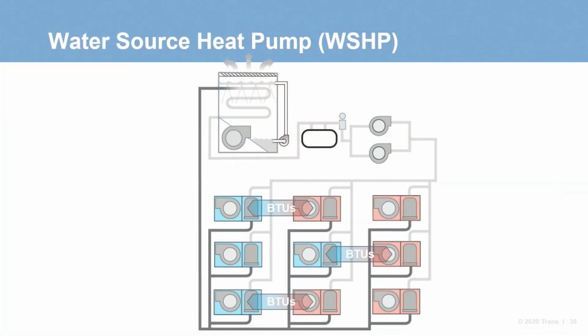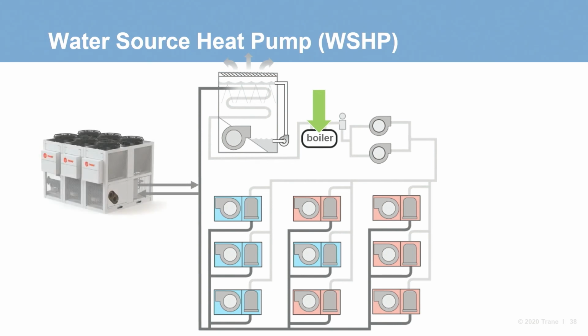On the other hand, if you have a building that already has water source heat pumps and uses a gas-fired boiler for loop tempering, this offers a potential target for electrification. That boiler can be supplemented or replaced with a heat pump chiller or chiller heater. Since loop tempering can utilize mild hot water temps, air-to-water heat pump technology available today is well suited for this application. Before we leave water source heat pumps though, one more note on retrofits.